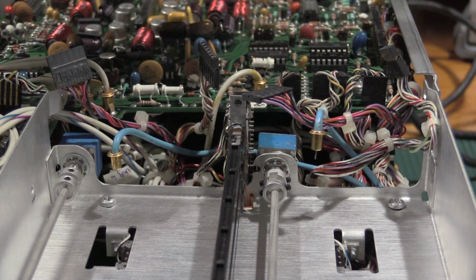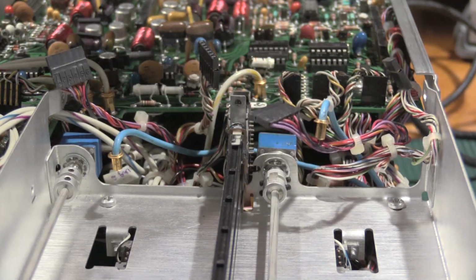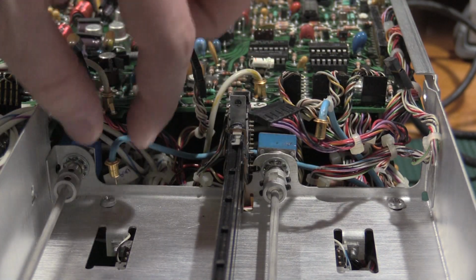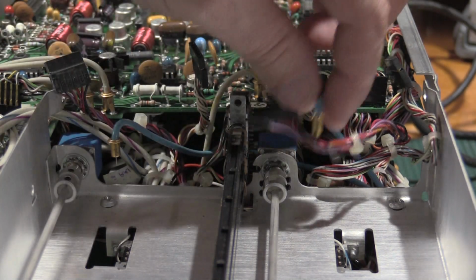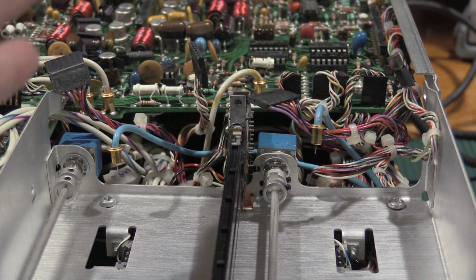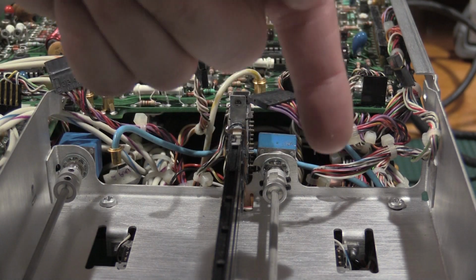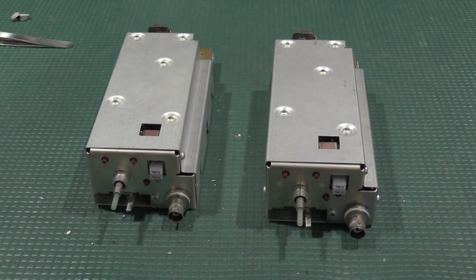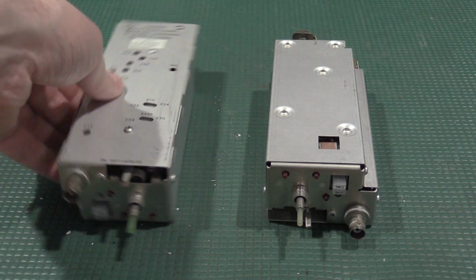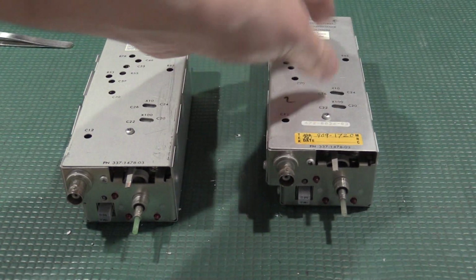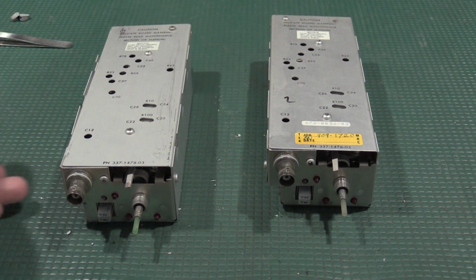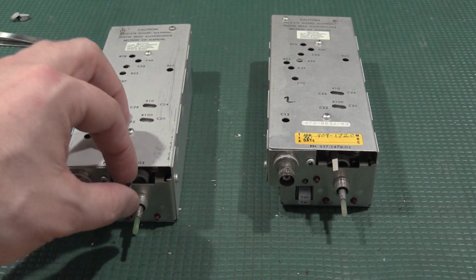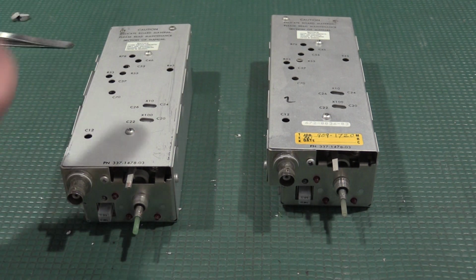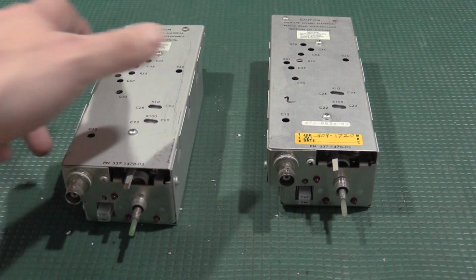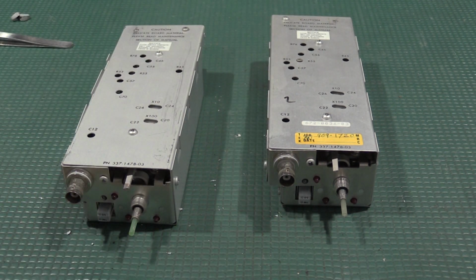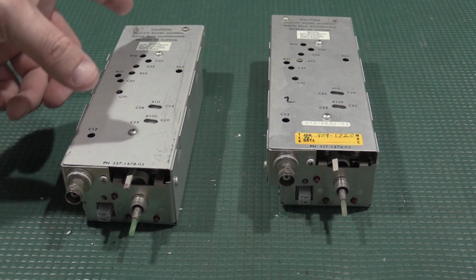And here's the back of the unit open. Each one's a wiring harness for one of the attenuators. So you have 2 plugs and one of the Tektronix micro coaxes that need to come out. Channel 2's on this side, channel 1 is on this side. Here are the attenuator sections for the 485. They actually come as these modules, so they're real easy to replace. I'm assuming this was done for serviceability, but if these were purchasable, they'd be real easy. You just swap in a new one, do a little bit of a calibration, and off to the races.